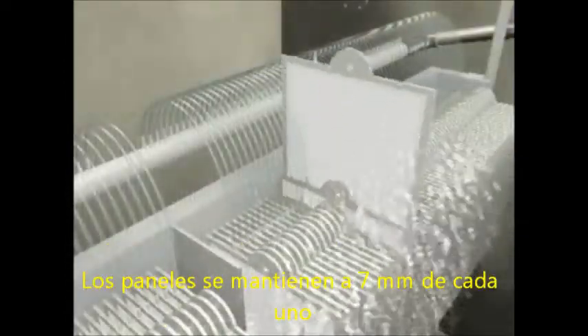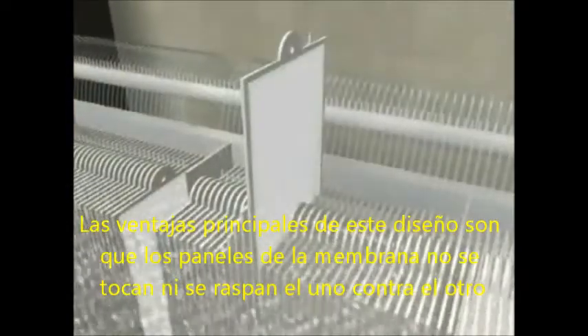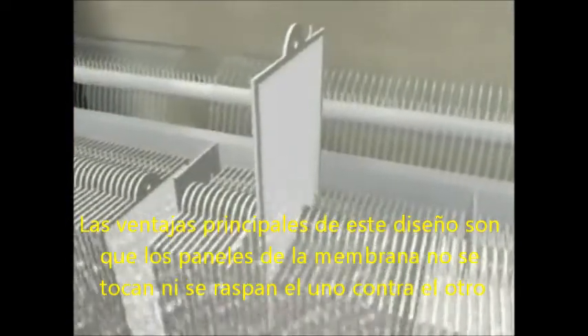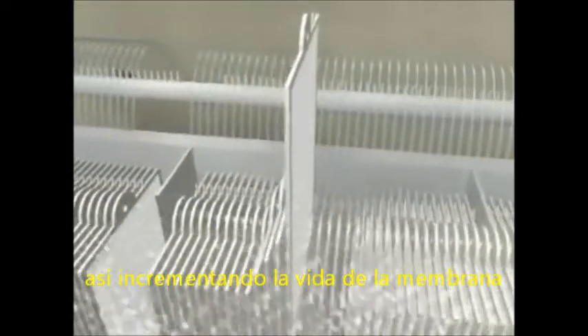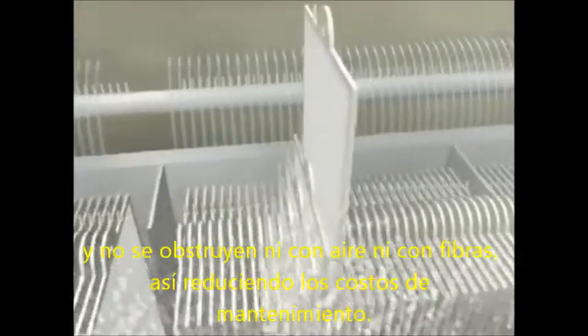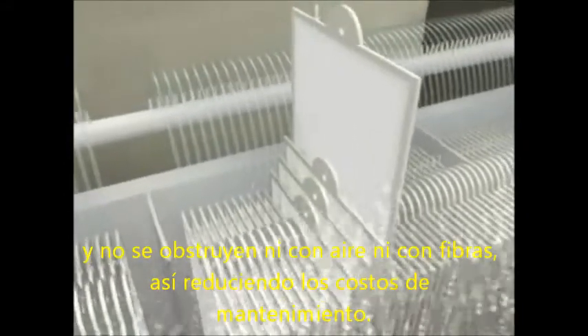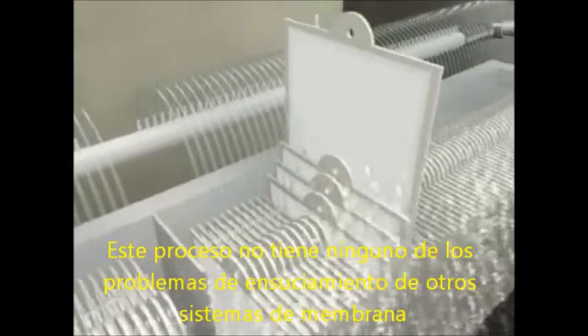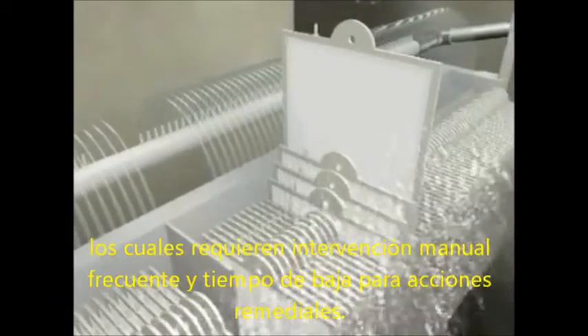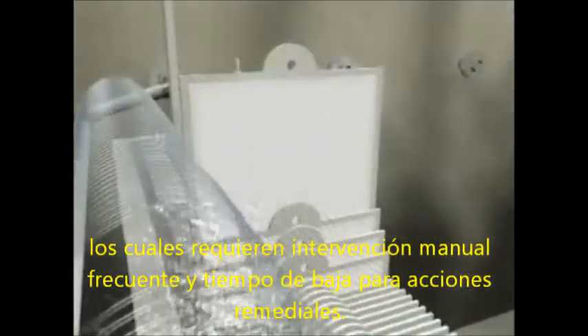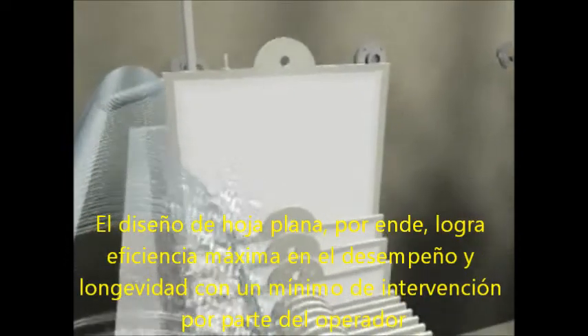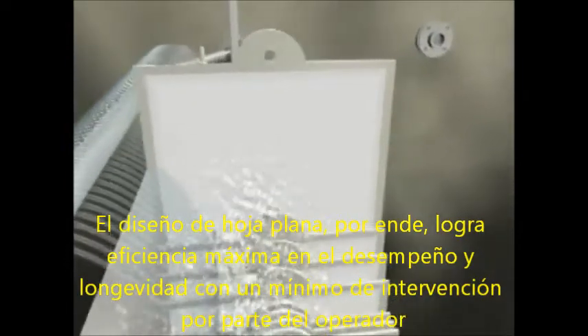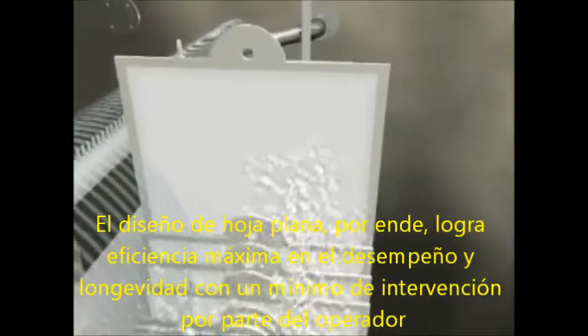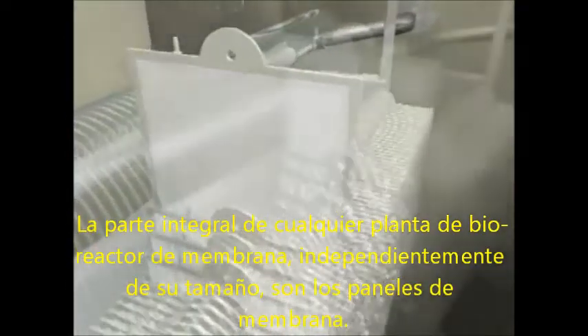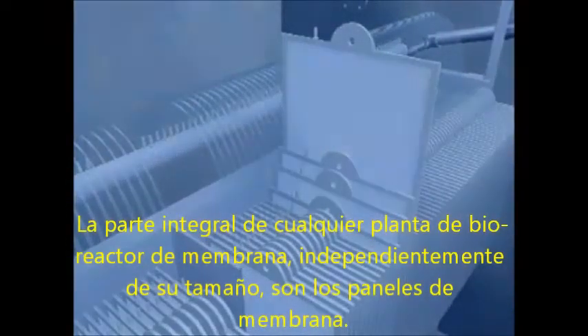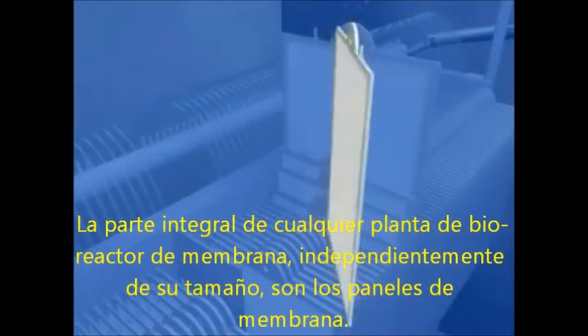The panels are held 7 mm apart, the principal advantages of this design being that the membrane panels do not touch or abrade each other, so increasing membrane life, and are not clogged with hair or fibres, so reducing maintenance costs. This process has none of the fouling problems of some other membrane systems, which require frequent manual intervention and downtime for remedial action. The flat sheet design therefore achieves the maximum performance, efficiency and longevity, with the minimum of operator intervention.